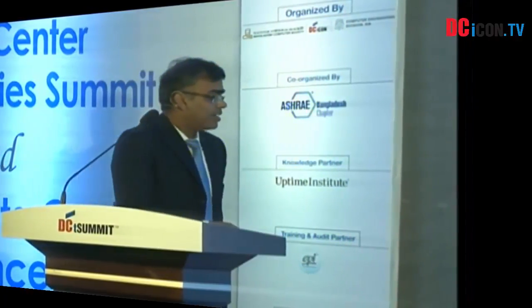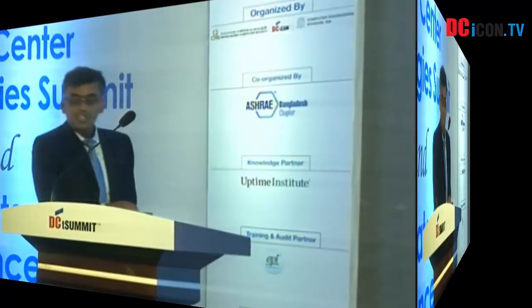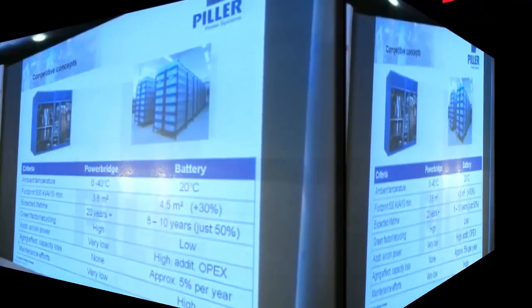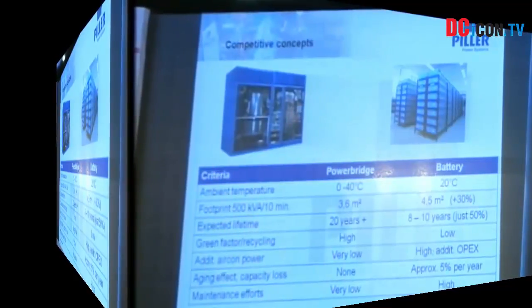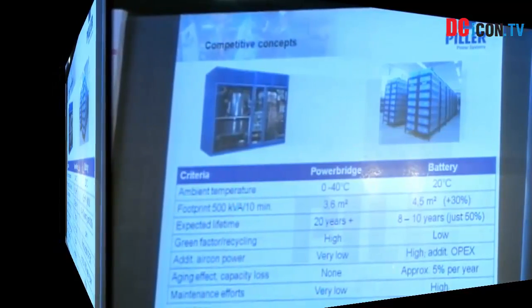Green factor: recycling is very high here, low there. Additional air-conditioning power is very low. You just need some cooling air, circulation of air inside the room. Highly additional operating expense for batteries. Aging effect, there's none here, whereas there it is approximately 5% per year. Maintenance effort is low. You only change the bearings, whereas there you have to replace the equipment itself. You have a lot of maintenance equipment to look at. And one more factor which I have not mentioned here: batteries are the most unreliable equipment in any data center. An analysis was done by Emerson last year, and according to the database, almost 55% of the failures in any data center are attributed to battery failures. So with this power bridge, you don't have any failures at all.